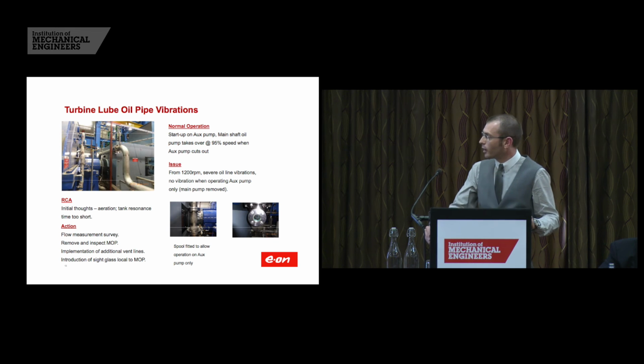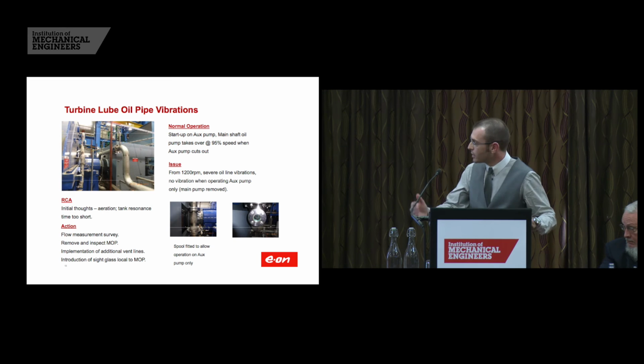But during the removal of the main driven oil pump, so we could keep forward momentum with the project, which is one of the main things that you have to do, we just introduced a spool piece, which allowed us to run the plant on the auxiliary oil pump with a DC backup only. And this becomes quite a nice strategic spare in the future. If there are any problems with the main shaft-driven oil pump, we can simply replace it with this and keep operating. The machine was rebuilt with the new vent lines, confidence in the main shaft-driven oil pump.